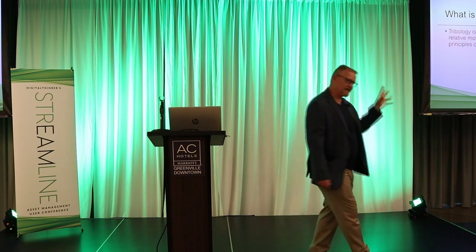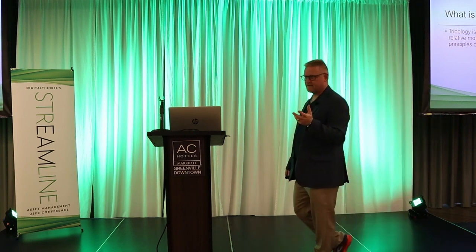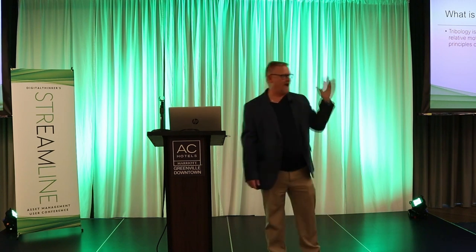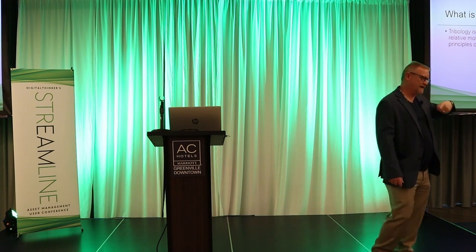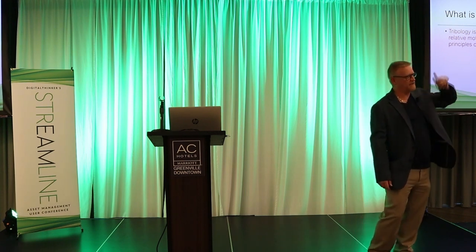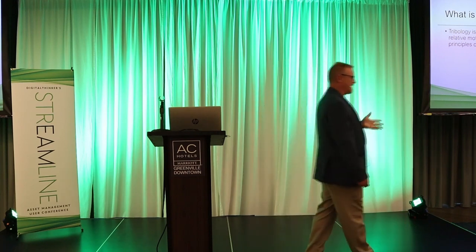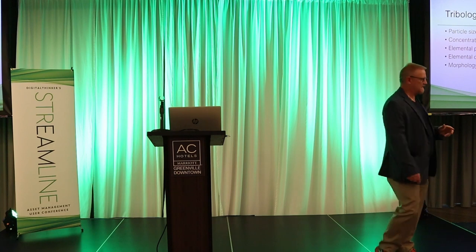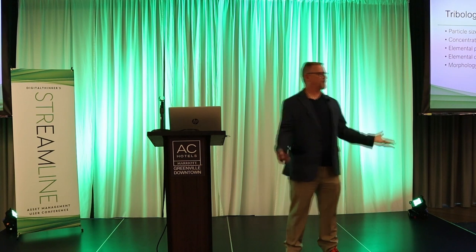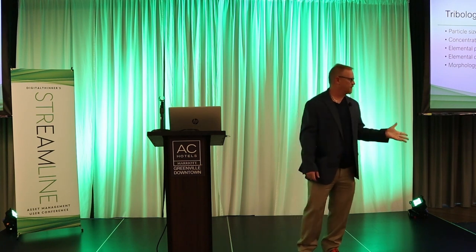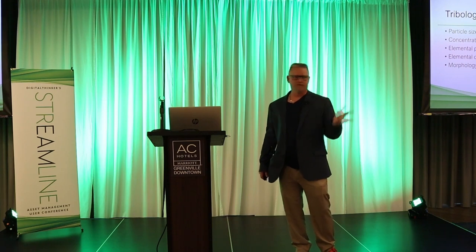That oil bath creates a coating around the spherical elements or roller elements and the inner and outer race of the bearing, which allows them to run smoothly. And they continue to go out of the oil bath and back in the oil bath over and over again. Tribology looks at 2 major factors. It looks at whether or not the lubrication still has its lubricating properties, which means, is the lubricant still good enough to create a film thickness around the roller element?